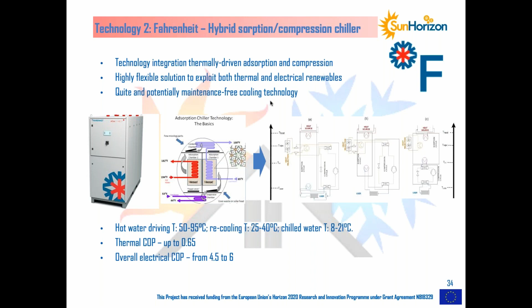The second task is about optimizing the integration of the vapor compression with the absorption machine. There are different possible options, such as pre-cooling, parallel integration, or cascade integration. In SunHorizon, together with Fahrenheit, we selected parallel integration, so both machines will work in parallel. The prioritized one will be the absorption machine, driven by solar heat provided by TVP Solar thermal collectors, while the vapor compression machine will integrate the additional cooling capacity needed.